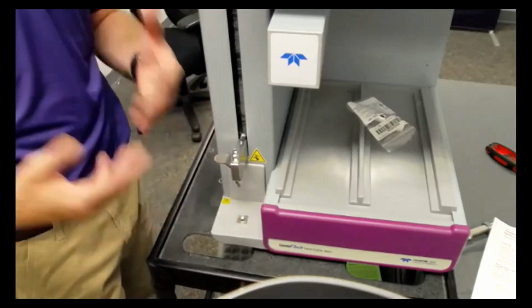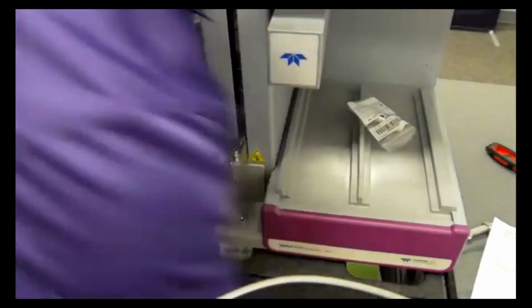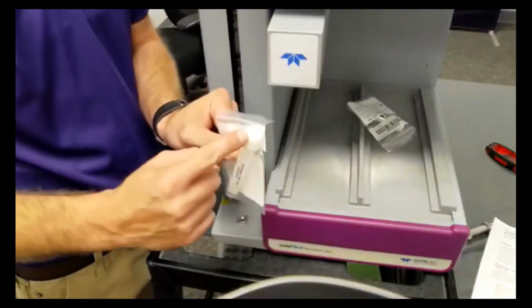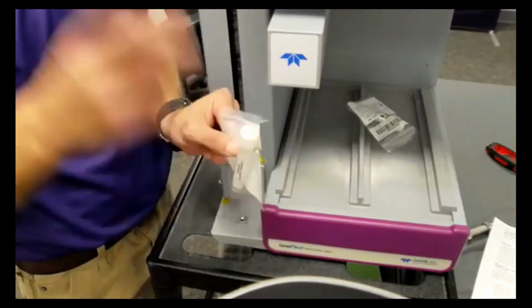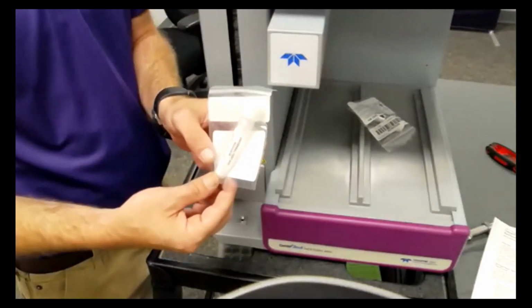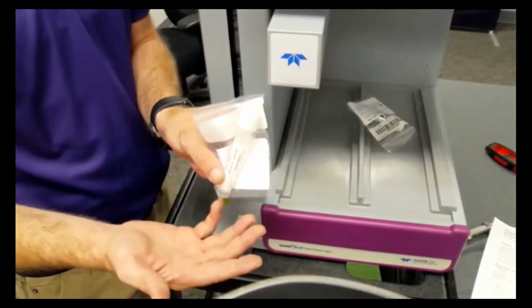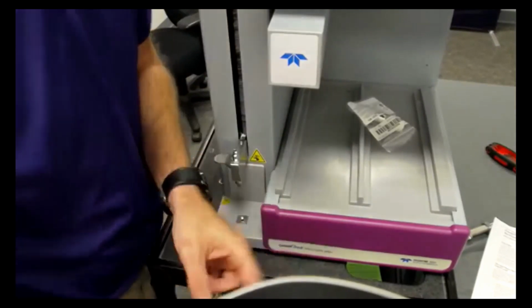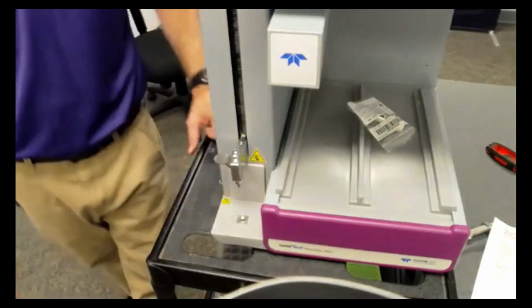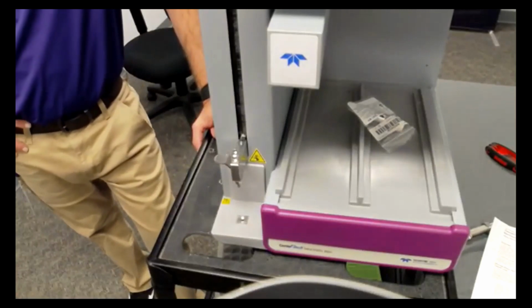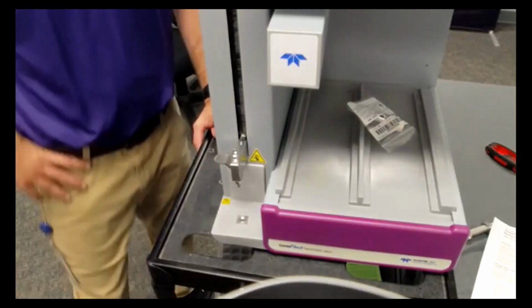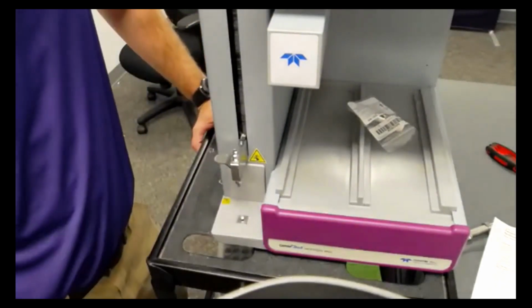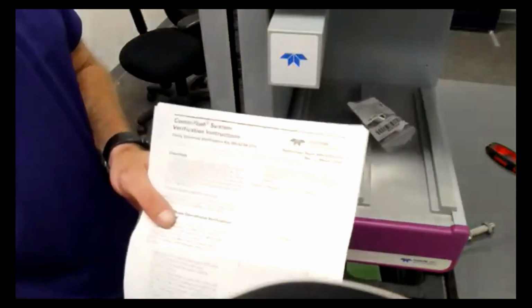So then you start to wonder, did maybe I get all my sample fully dissolved? Sometimes when you inject in here, you might have some sample blow out as a powder. Okay. Little things like that can affect your chromatography. So they're not going to be perfect. The universal test mix will not be perfect, but we do have a general area time frame that we're looking for these peaks.